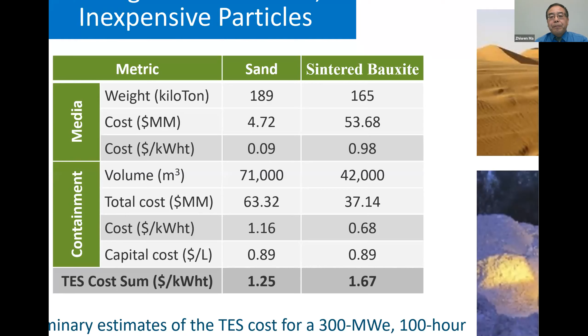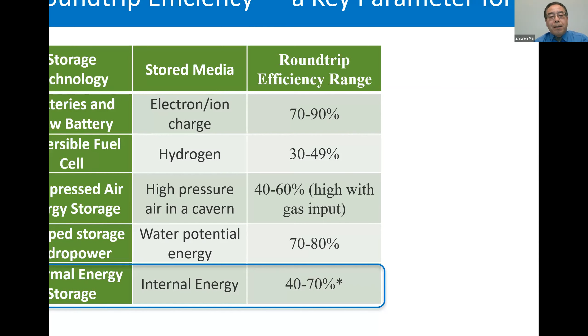Another key parameter for energy storage is the round-trip efficiency. Battery claims a pretty high efficiency, but battery efficiency varies. The reason is that the higher the current drawn, the more irreversible losses in the internal resistance and polarization will occur, which lowers the battery efficiency at very high power discharging. So it's a range. And people have also studied compressed air energy storage a lot and claim 60% efficiency. My study found that if there is no heat recovery from the compressed air, the heat is dissipated, and later natural gas is needed to reheat the gas back to the turbine, and that 60% a lot is coming from the fuel heat. So the electric-to-electric efficiency is very high, but the energy efficiency is not significantly high.